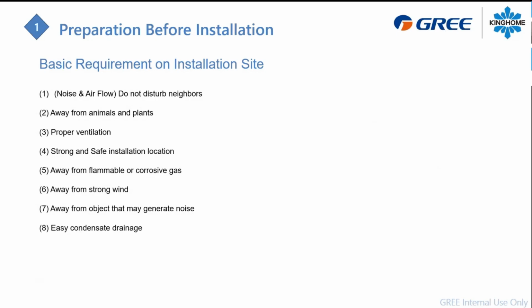So when you are on site, you want to make sure that when you locate this outdoor unit or your indoor unit, you will be aware that the noise will not disturb the neighbor, to have proper ventilation around the unit, to make it a strong and safe installation, away from flammable or corrosive gas, away from strong wind. This is the one I want to highlight a little bit, because in heating mode you don't want to let the wind do the job of the outdoor condenser fan. So just be aware that staying away from strong wind is important. Also away from objects that may generate noise, and high enough to have easy condensate drainage.